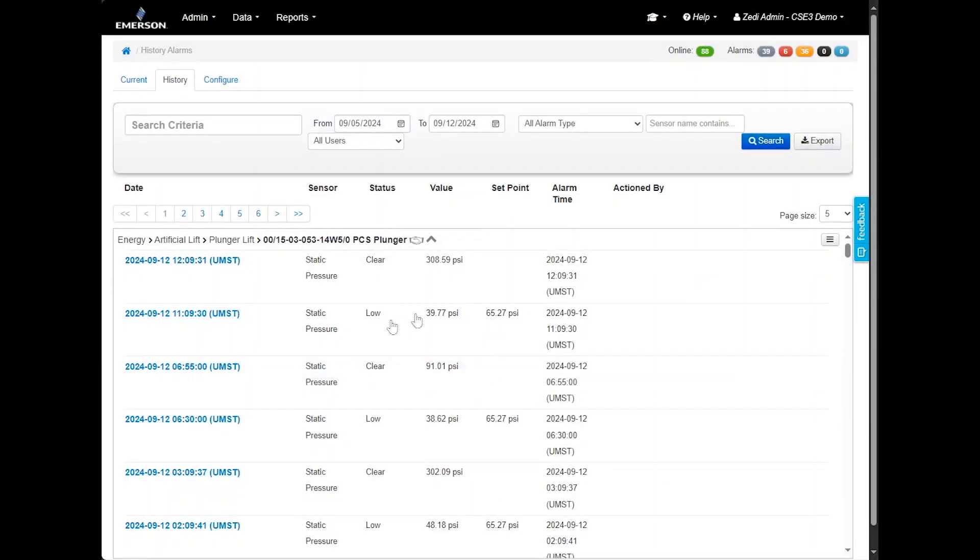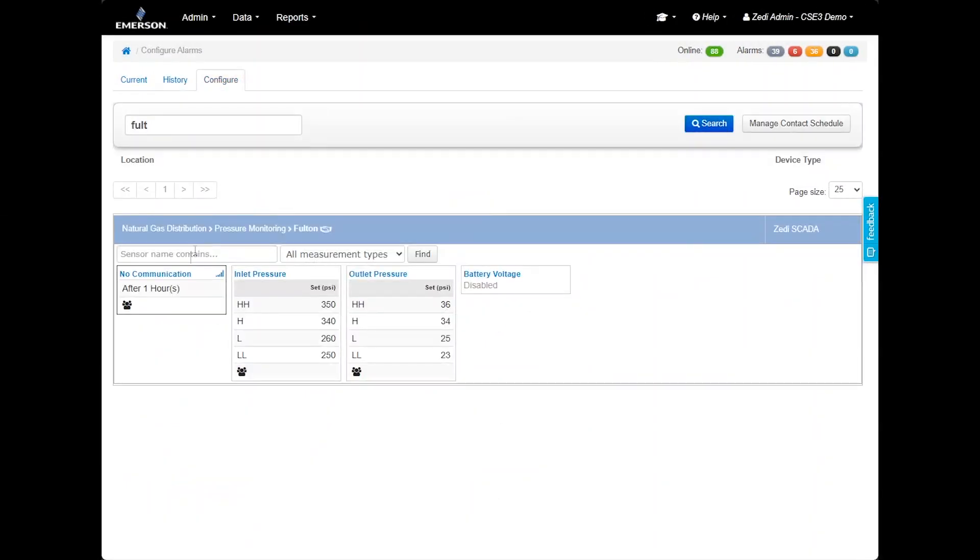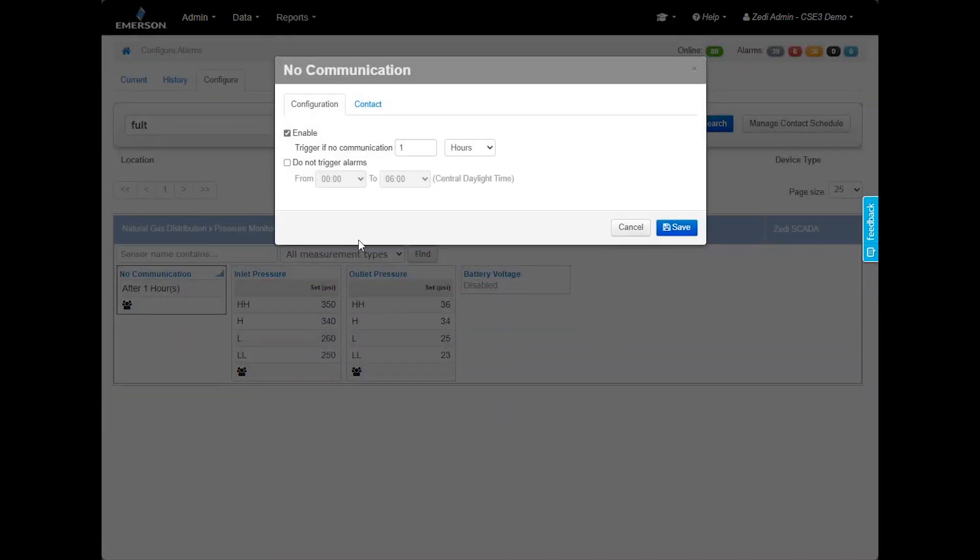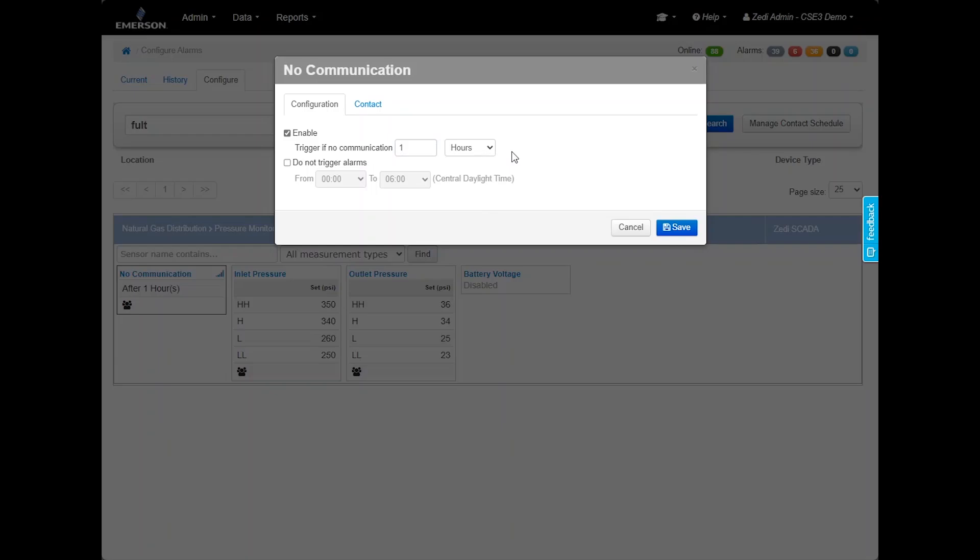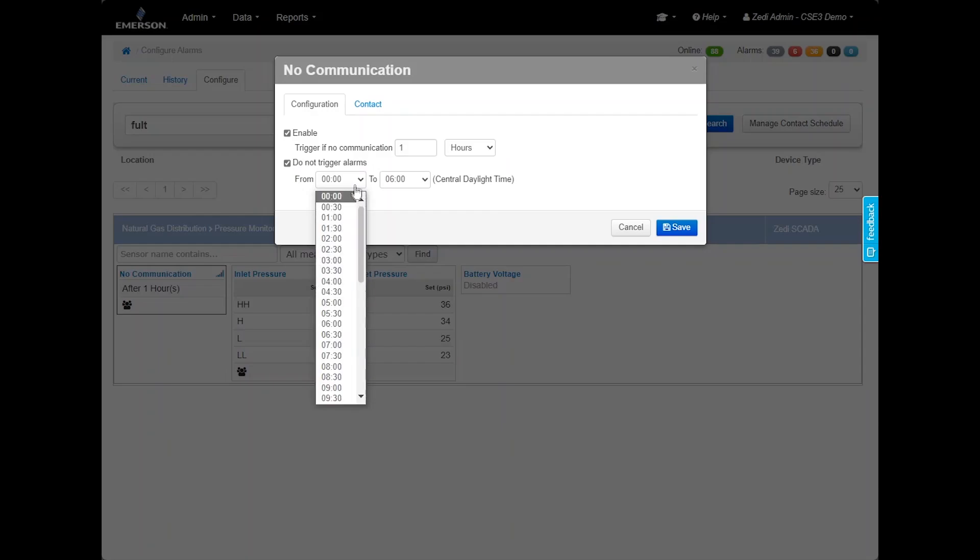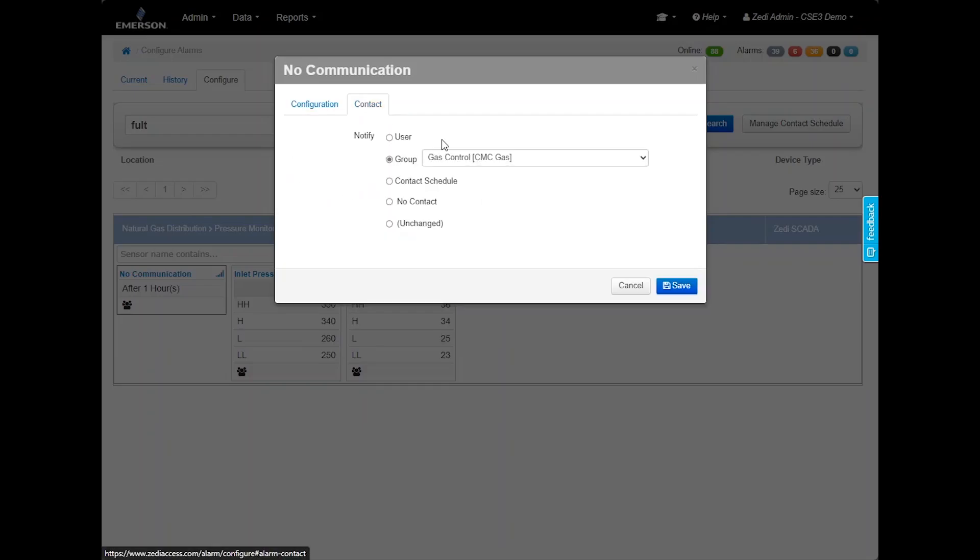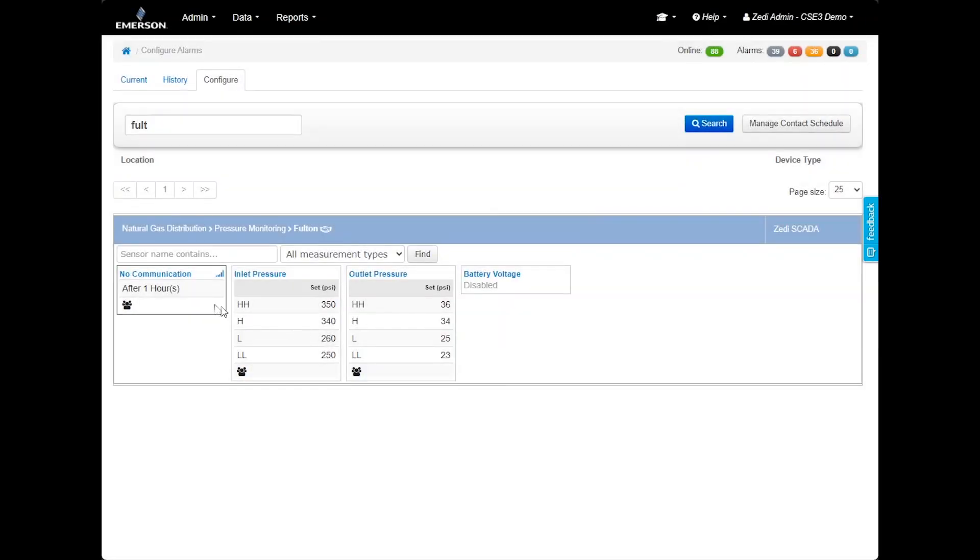You can configure and edit alarms. By selecting a location, the alarms for that location will be displayed below. The first alarm type is the no communication alarm. This alarm is triggered when a device has not transmitted into Zedi SaaS SCADA server for a specified number of hours. The default is 24 hours of no communication between the device and Zedi SaaS SCADA. To configure this alarm, select no communication and set the threshold for the number of hours without communication. You can also specify a do not trigger alarm period during which alarms will not trigger. For example, you might set this period from 10 p.m. to 6 a.m. so that no communication alarms occurring during this time will be delayed and sent out at 6 a.m. instead. Select Contact and set who receives this alarm. Select Save.